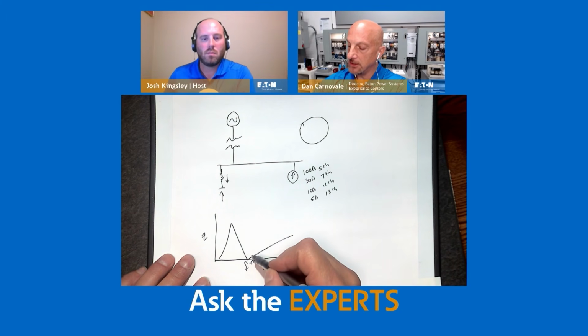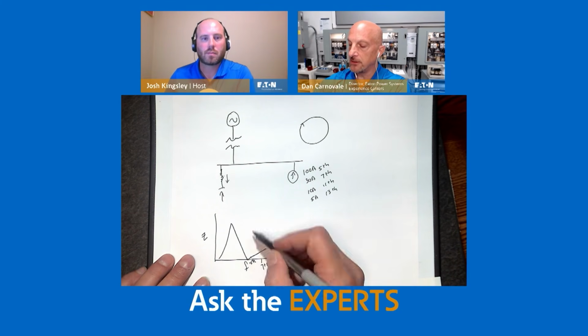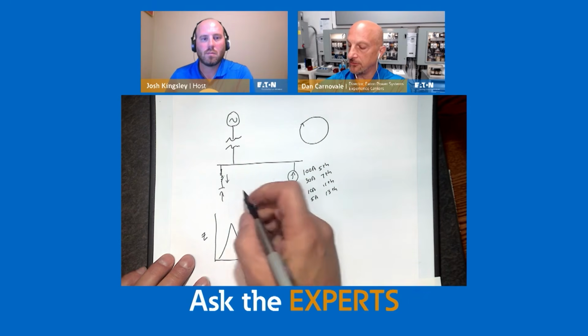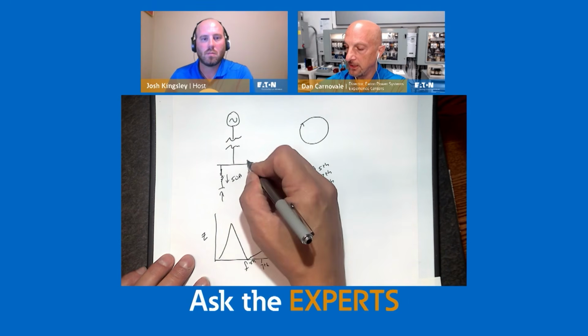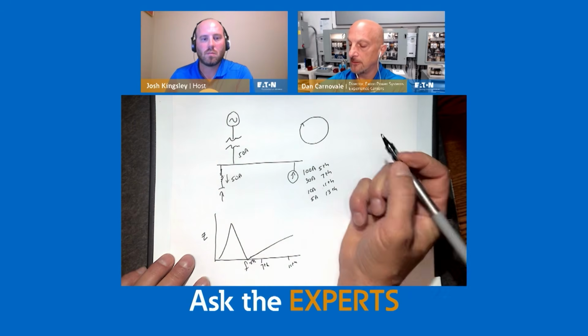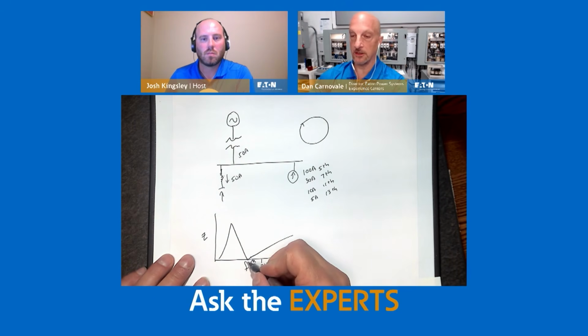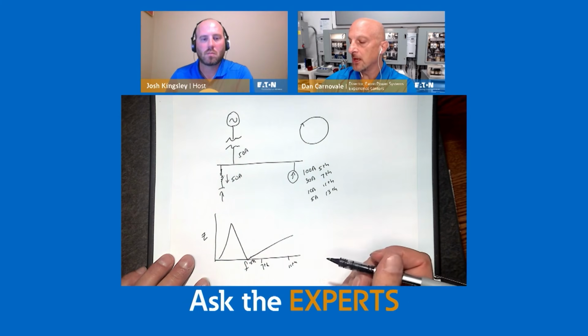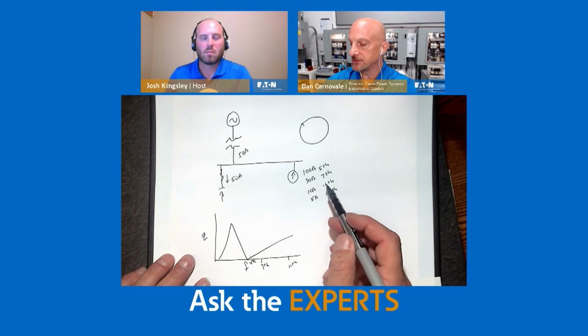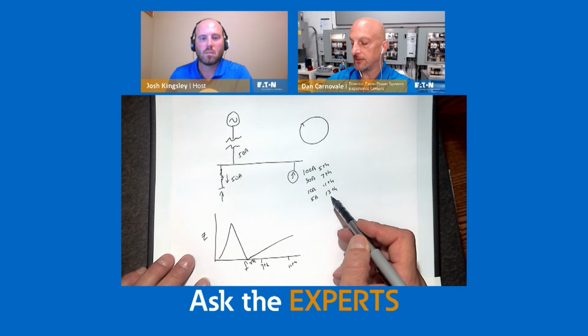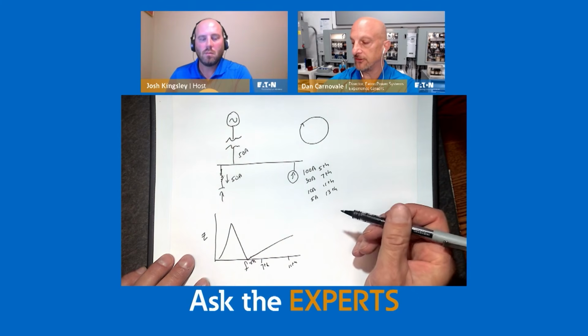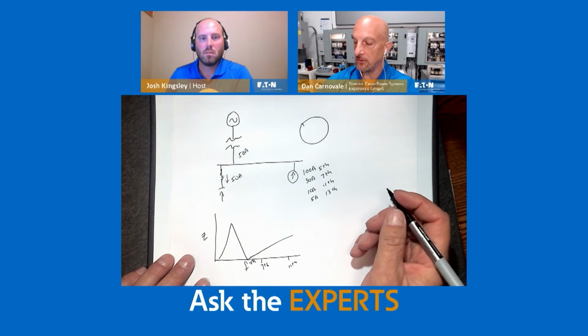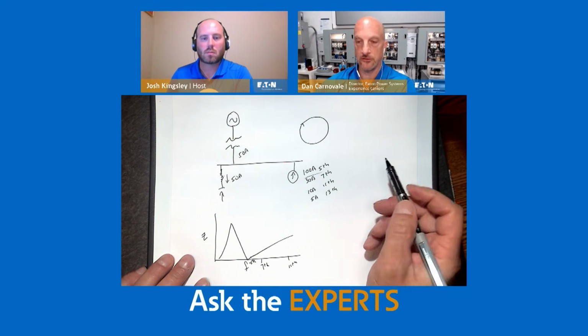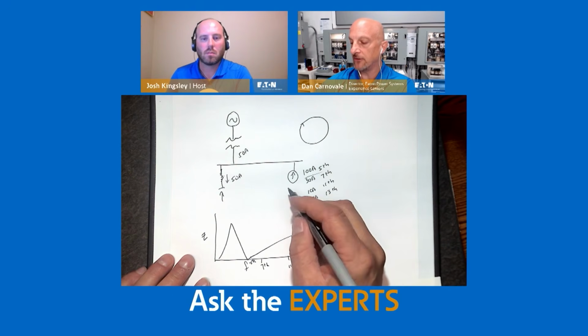You're going to get a decent amount of fifth through it. So maybe instead of 100 amps going there, maybe you have 50 amps here and 50 amps there. And then you would determine the losses in that, which is going to be minimal because that resistance is fairly small. But you're not going to get rid of much of the 7th, much of the 11th or the 13th. So they're going to want to still flow back in the system. The benefit, though, is the 5th is the biggest one. So we can get rid of that in a fairly simple way.